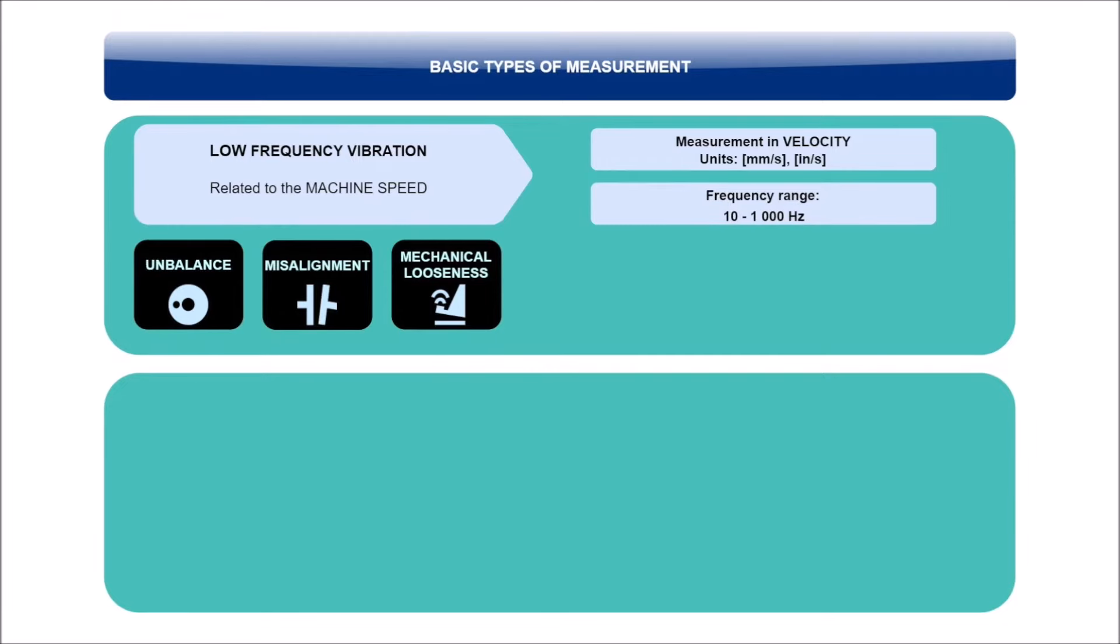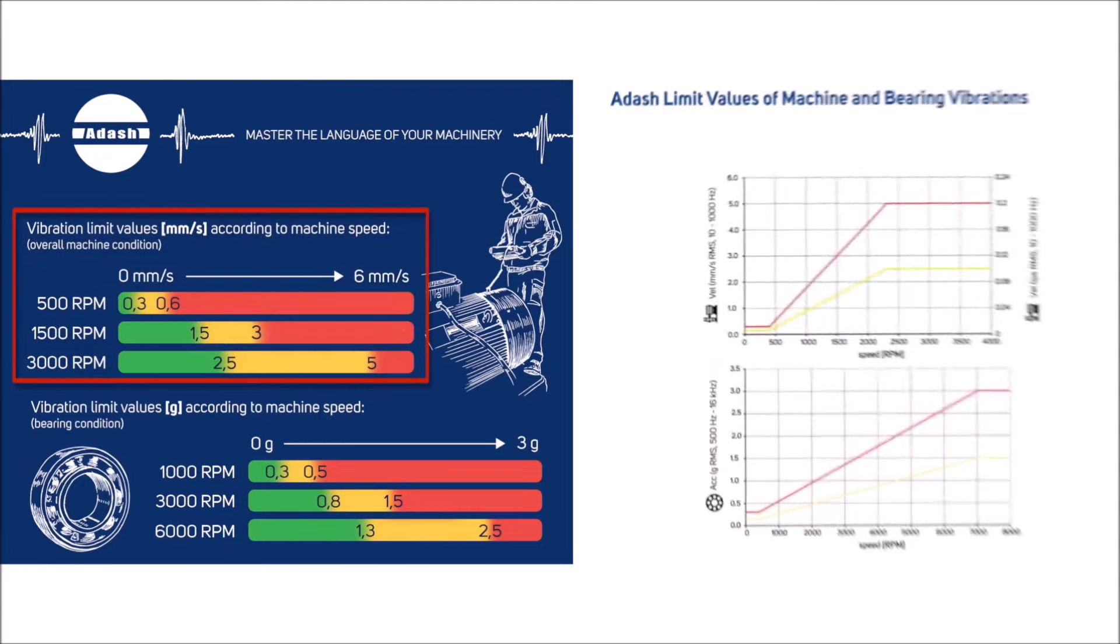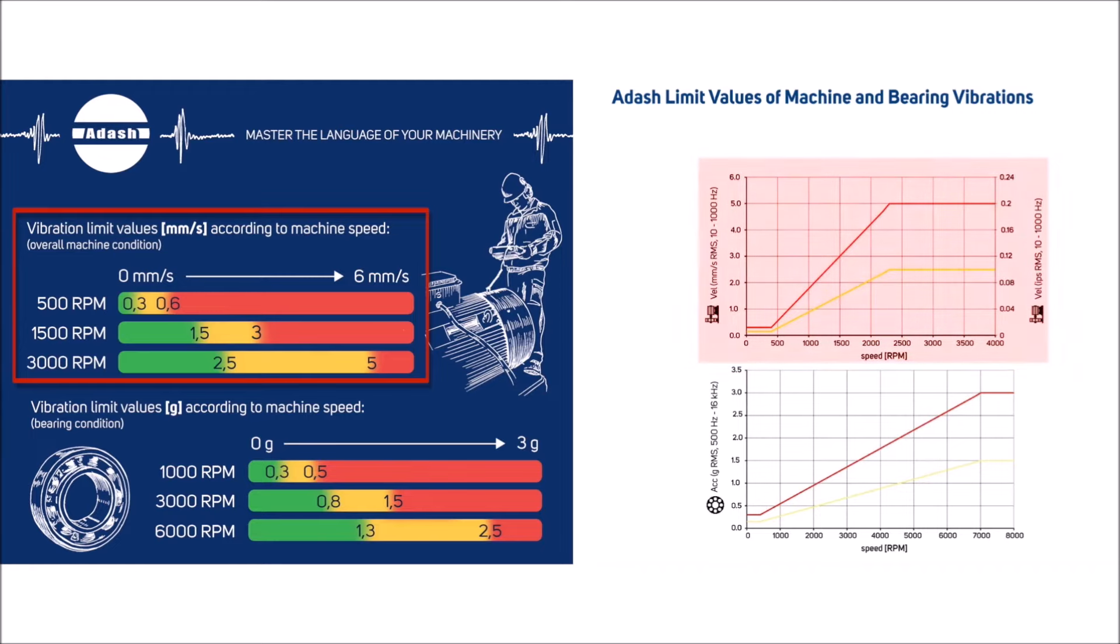This frequency range is also applied on ISO 10816 standards. These standards take into account the size of the machine and its foundation. ADASH has defined vibration limit values which are related to the speed of the machine, not to the size of the machine. The frequency of 10 to 1000 Hz is also applied.